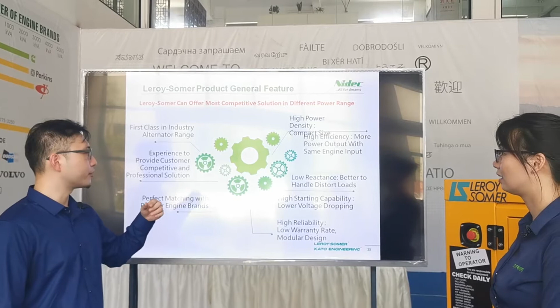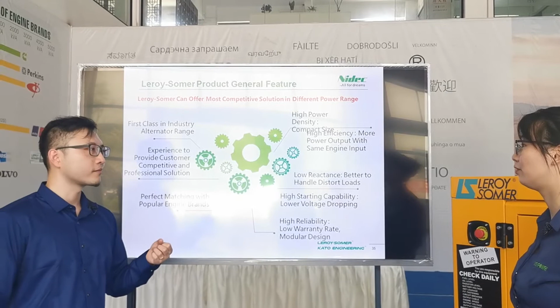Also high starting capability to limit the voltage dropping. High starting capability gives the benefit for special applications like motor starting, like pumps, because when the motor starts, the starting current for the alternator is very strong, so we need this function.